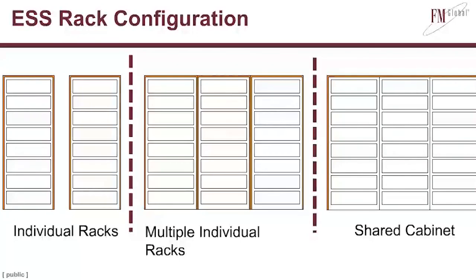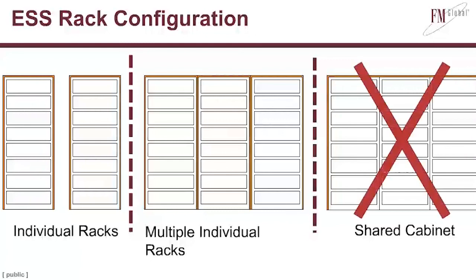The last thing here is just a comment on rack configuration. I've seen a few different rack configurations. The first one, on the left, is where you have an individual rack surrounded by a metal shell, a metal cabinet, and then you have some space separation, and then you have another rack. The next one is where you take those racks and push them together, but each one still has its own metal walls around the individual rack. And the third one, which I really hope we don't see, is where you take a bunch of racks that don't have any metal walls surrounding them, and you wrap the whole thing in a common skin. The downside is that you've taken away the barrier for the heat from the burning combustion in one rack to spread to its neighbor, and so this would make fire spread a lot easier.